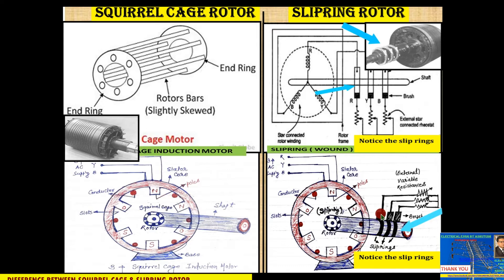The slip rings are made of bronze metal and are mounted on the shaft, insulated from it. Three carbon brushes are always in contact with the slip rings. Through these brushes and slip rings, external variable resistances are connected to the rotor circuit. This is the construction diagram showing both the squirrel cage and the slip ring motor arrangements.